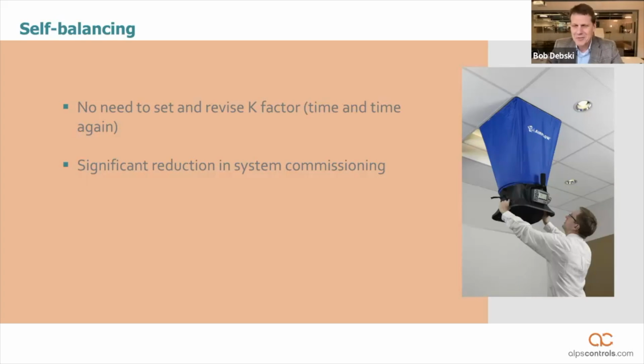That's not a construction site I've ever been on, but they're making it look like it's rocket science and precision. Well, that doesn't make sense, because that K factor that he's adjusting is basically a fudge factor to make sure that whatever reading the air balancer is seeing on the hood side is recorded on the flow sensor side of the DDC controller. The smart air valve does not require a fudge factor. The airflow measurement is so accurate, it can actually measure its own leakage. So at that point in time, there is no balancing required.